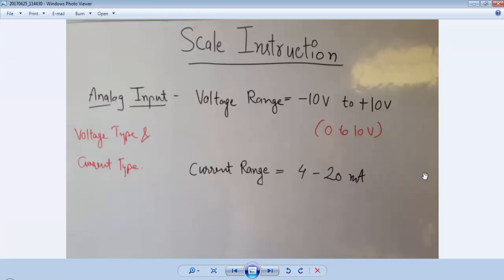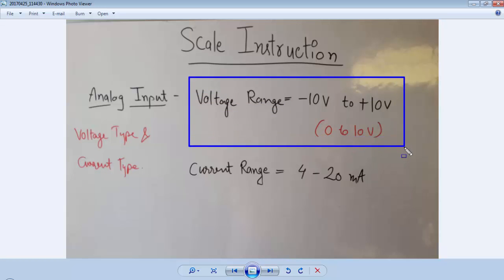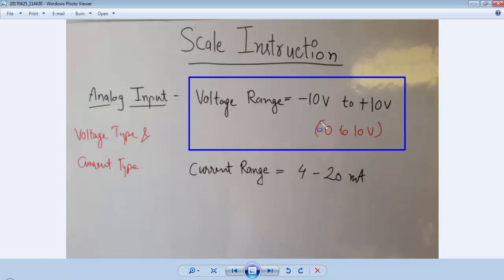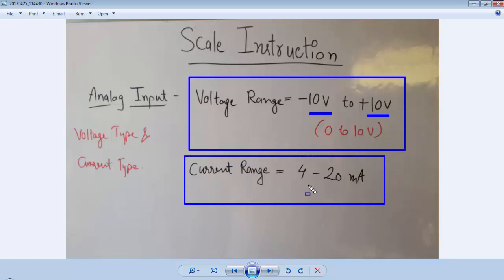For a PLC device, if we are dealing with analog inputs and outputs, we have two types of analog input/output cards. Either we can go for a voltage type card or a current type card. For a voltage type card we have a range of minus 10V to plus 10V DC, and for a current card we have a range of 4 to 20mA.